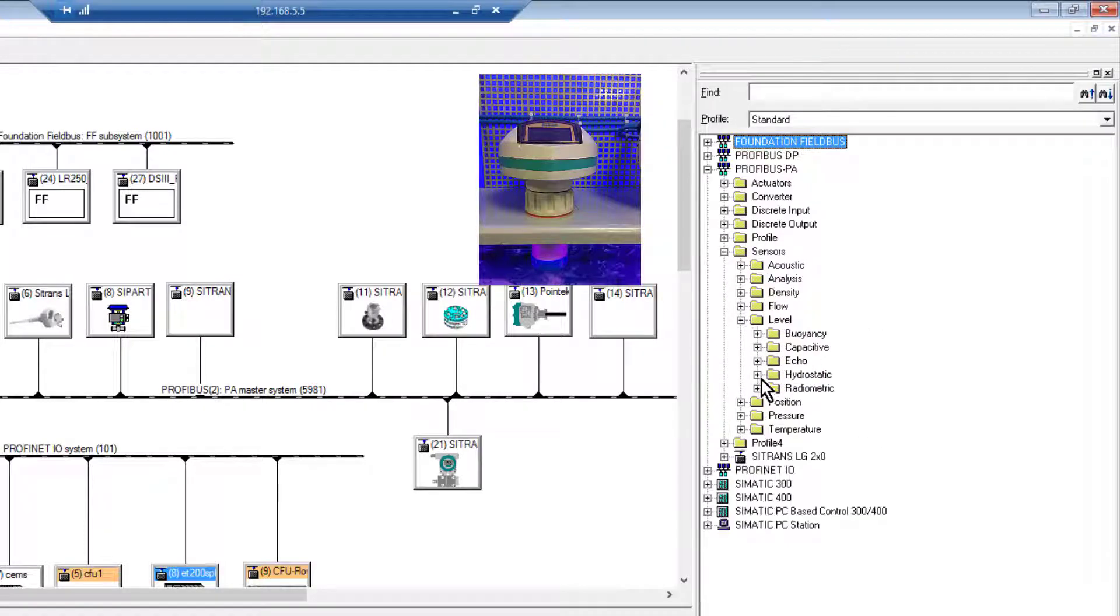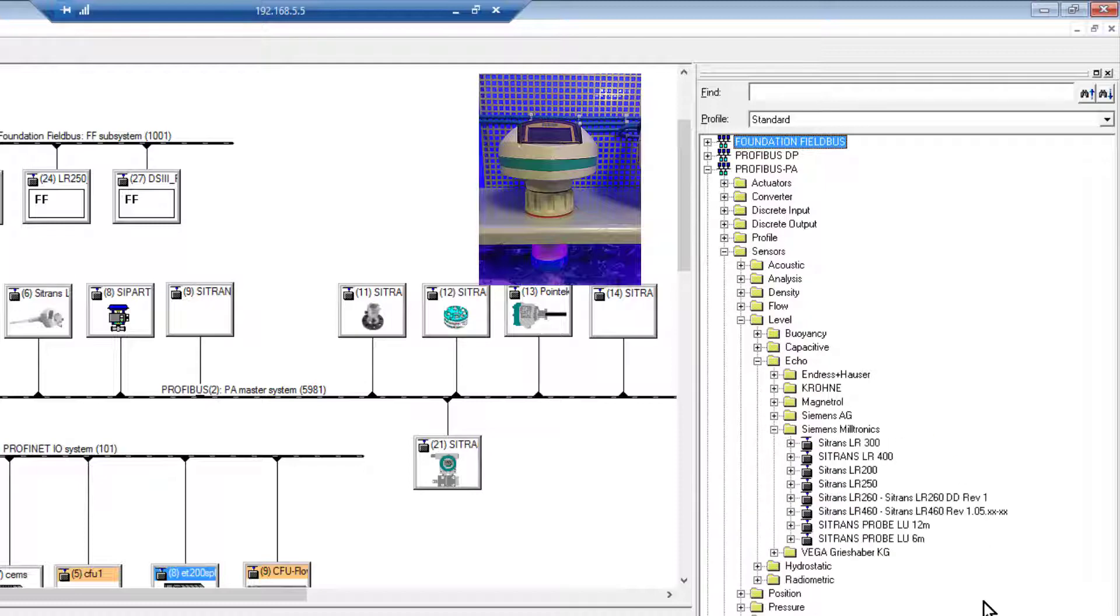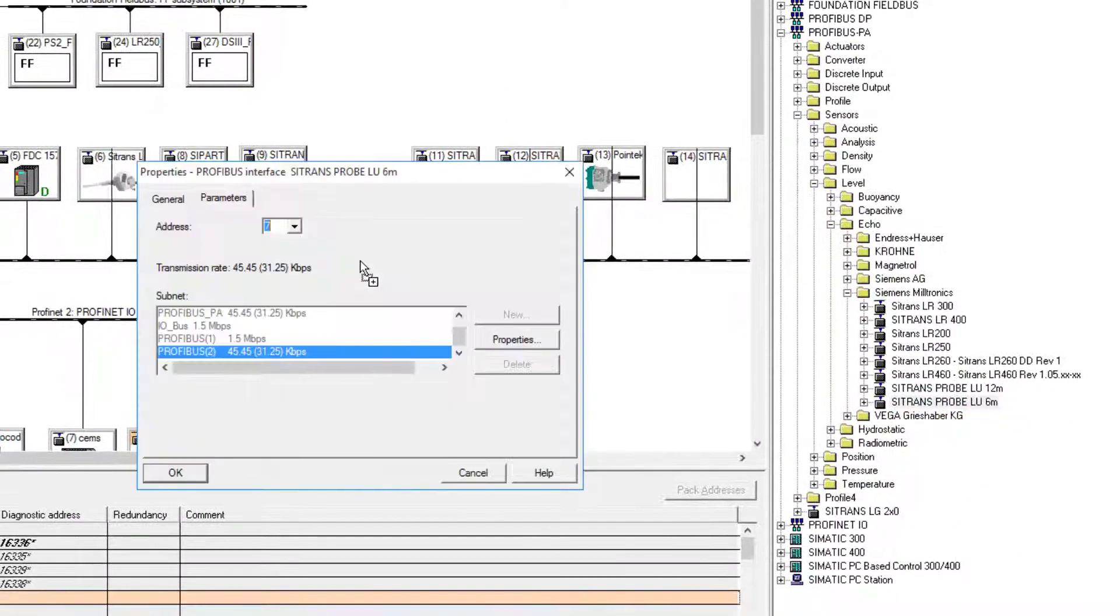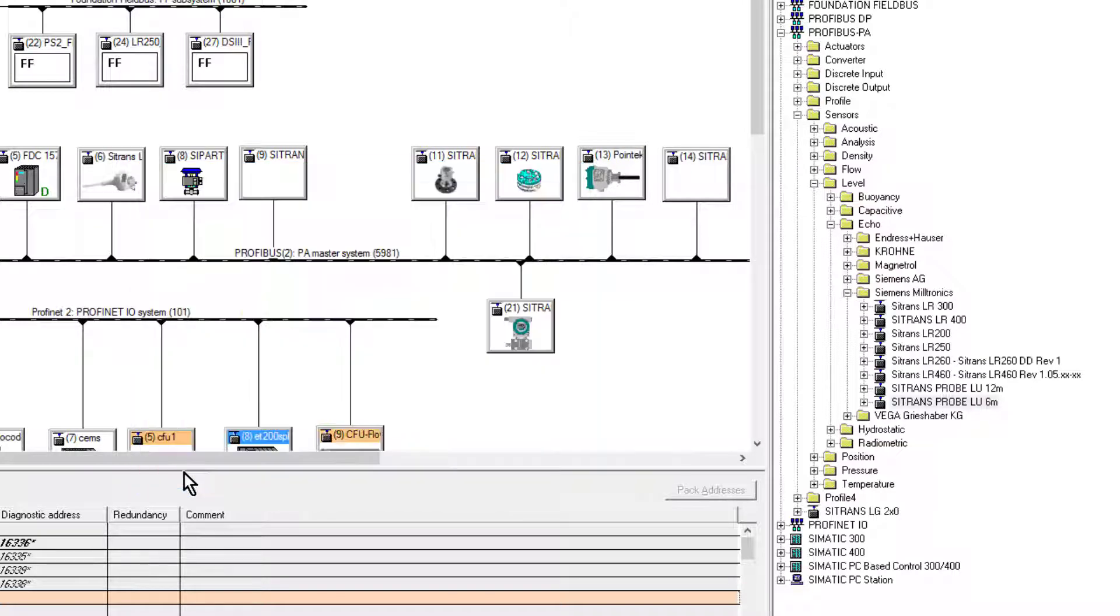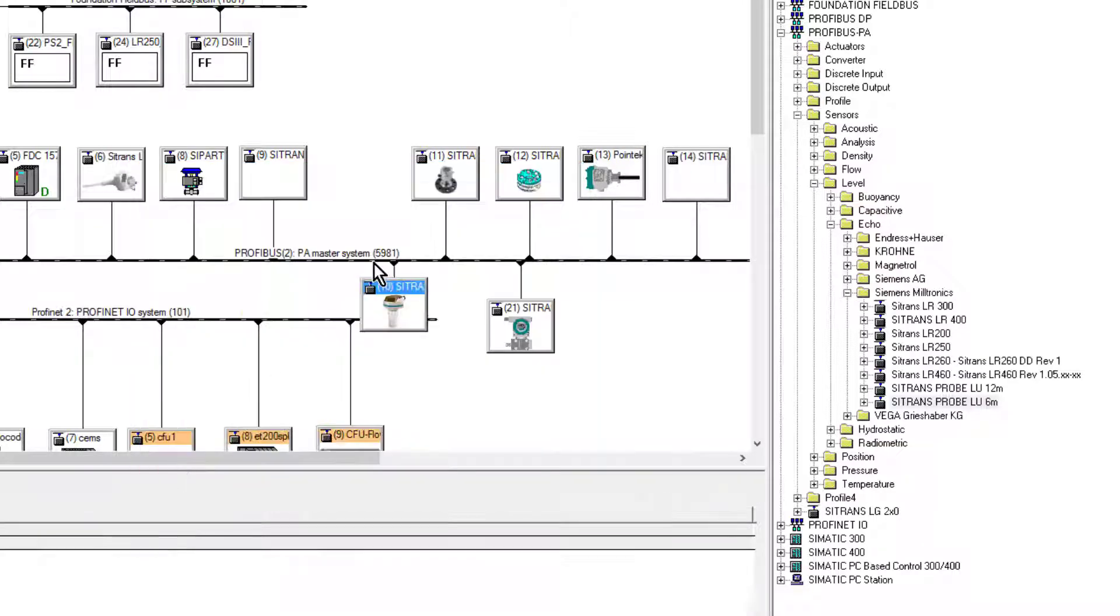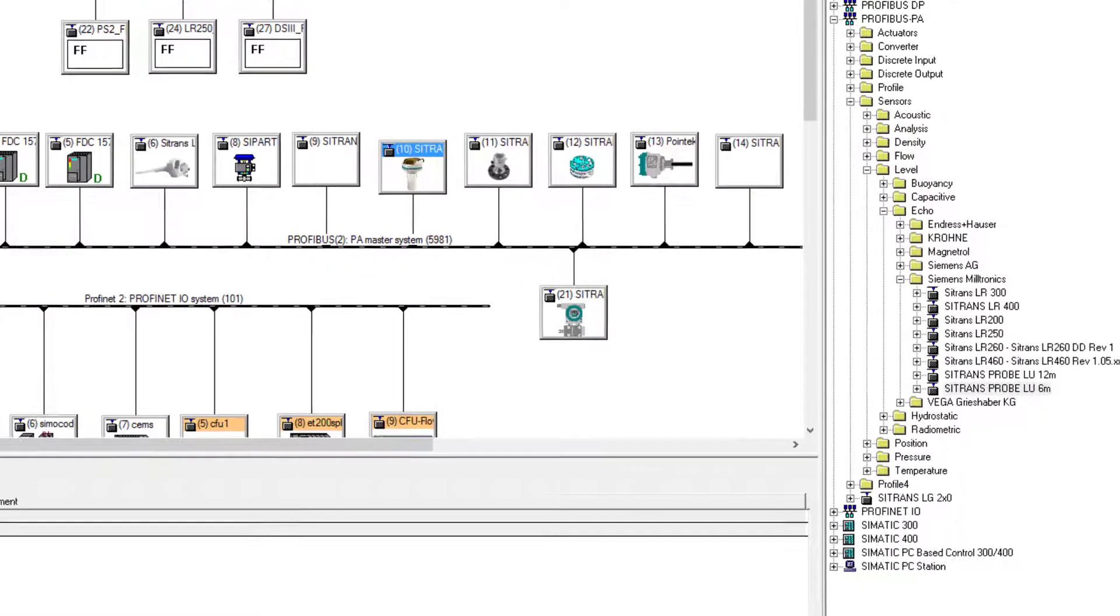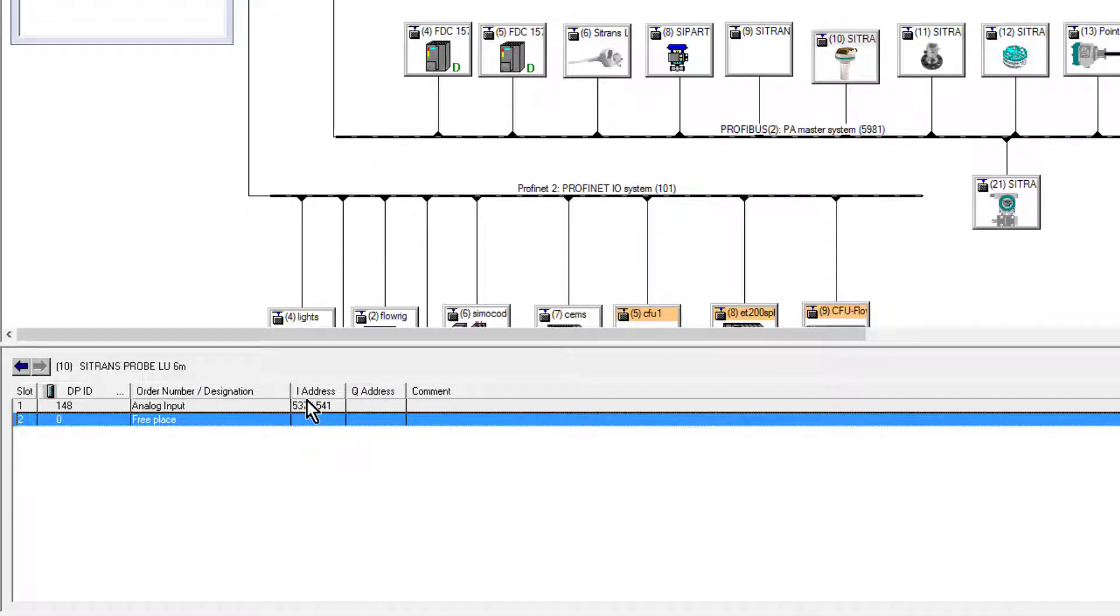It's a level sensor, six meter probe. I'll drag that onto the network and give it the address of 10, which is the address programmed on the unit. Then the only other thing I need to do is have a look at my analog block.